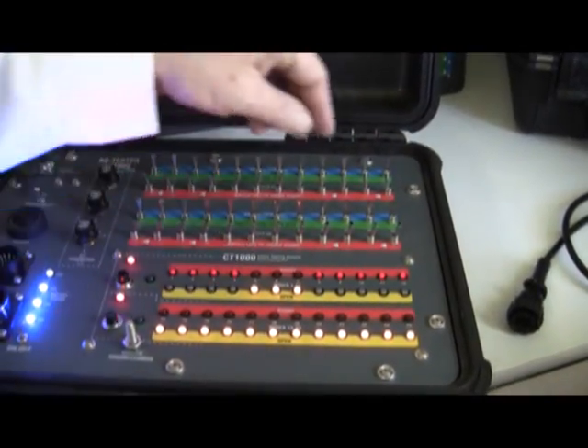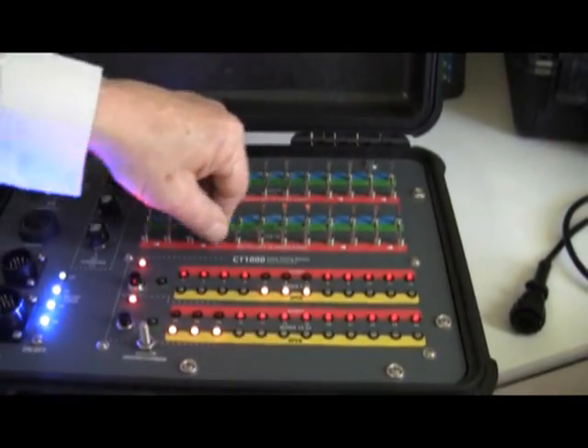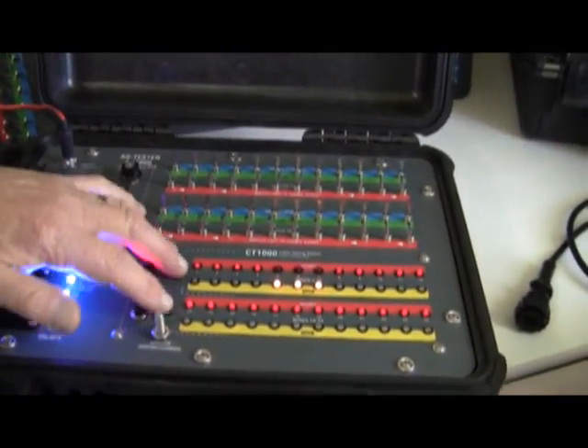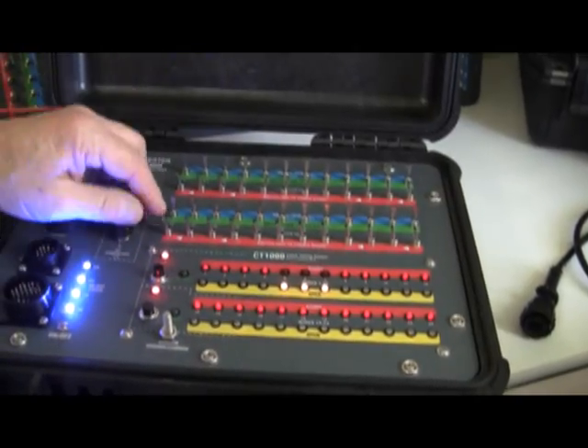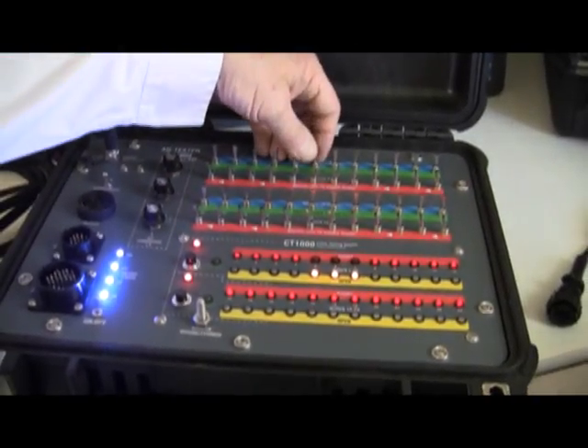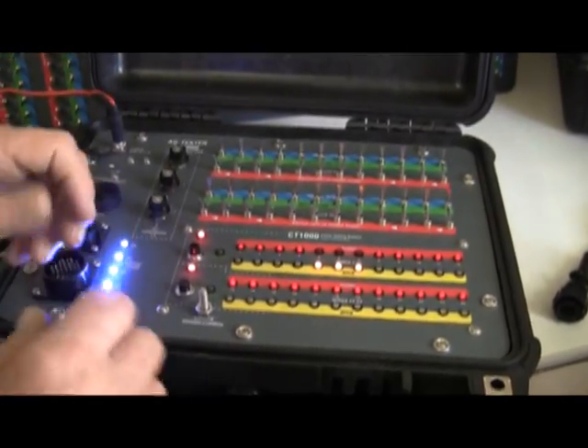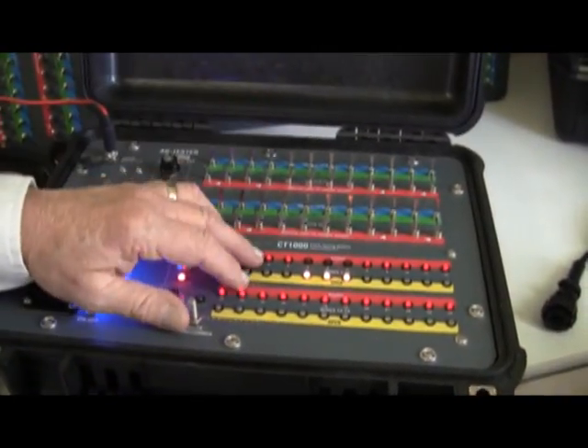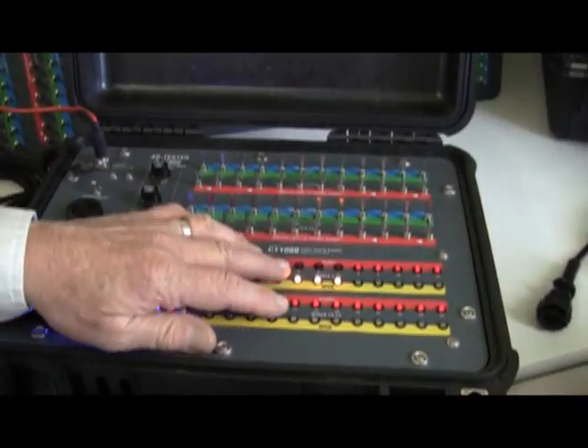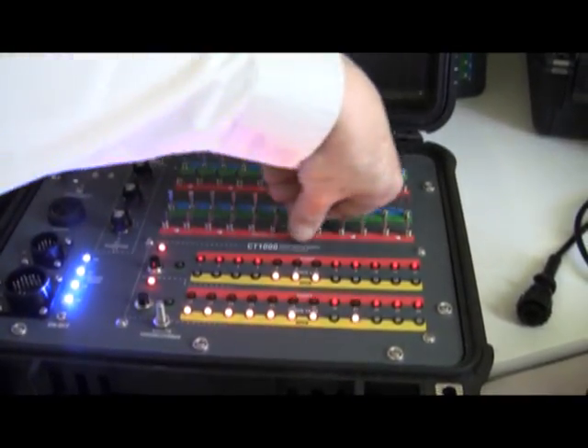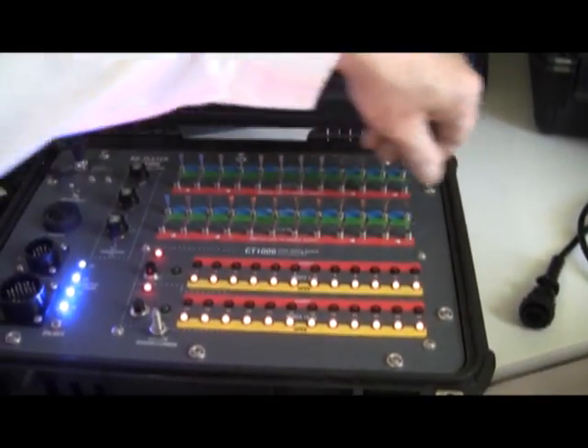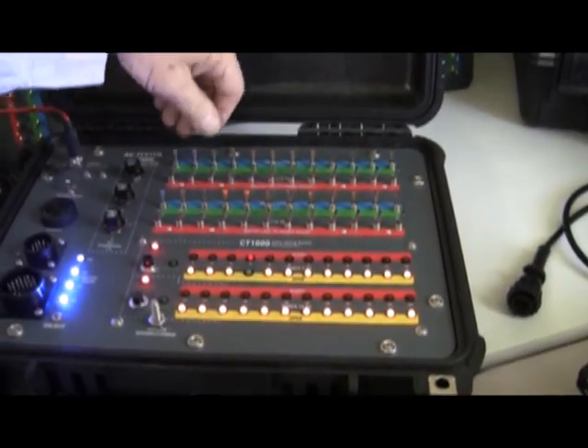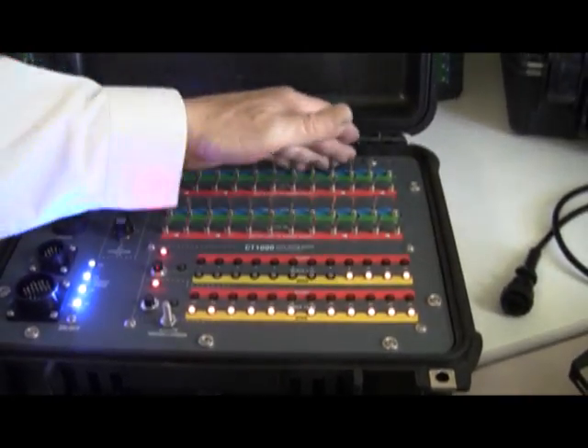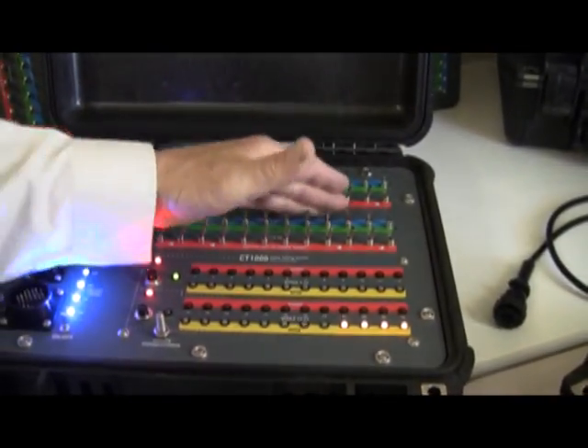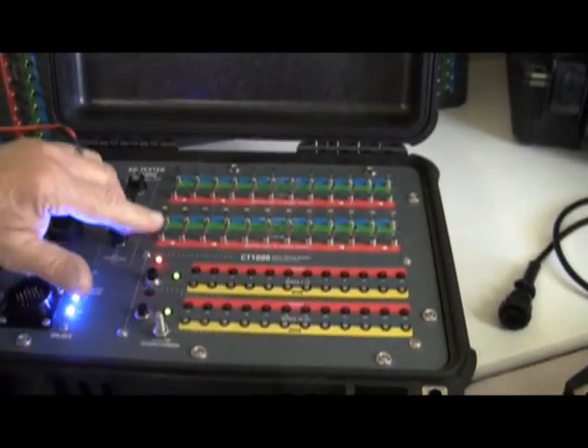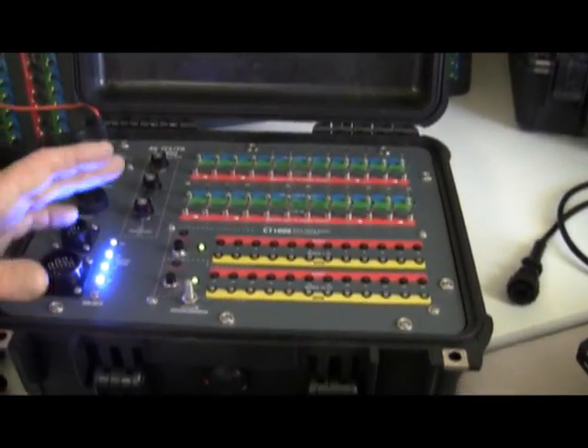Now I have a short condition - all the other wires are shorted back to common or ground, except the three we're interested in testing. We can then gently move the wire until we see an issue come up, which takes us through the diagnostic process. Put them all back in the no-short condition, shut them all down, and reset. That's a real quick overview.